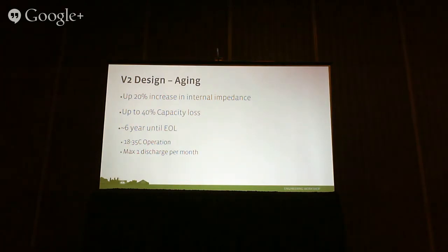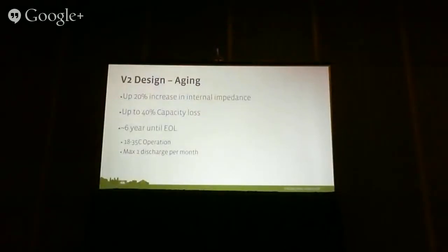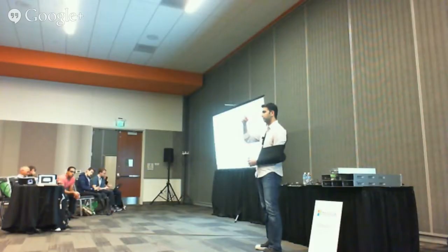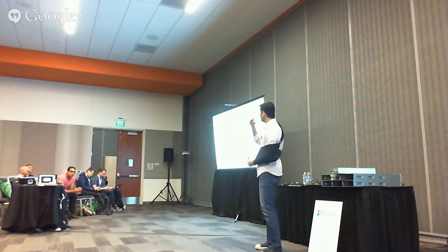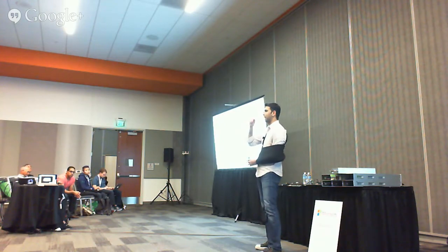Shipping and storage definitely matter too. Storage temperature actually directly affects the aging of the cell, so that needs to be considered. With aging of the lithium ion, there are two aspects: one is the increase in internal impedance, and the other, often not considered, is the capacity loss. We expect a 20% increase in impedance and a 40% decrease in capacity.